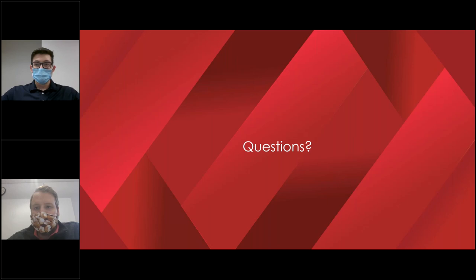Yeah, thanks, Stefan. That's a great question. NIST verification is sort of like a gold standard when you're getting your machine professionally verified. This is a very thorough program that NIST has for Charpy testing, and it uses indirect verification. So what they do is they precisely machine these specimens internally, document them, and then they send them to you to run on your impact tester. And then after you test your specimens, you'll send them back to NIST, and then based on how the specimens broke, they can determine some things like how aligned your system is, if your supports are worn, or you need to fine tune any parts of your machine like the hammer or your strikers. And then after they determine all these, they will send you a verification sticker with your lower range and whether or not you pass the NIST program. Good question.